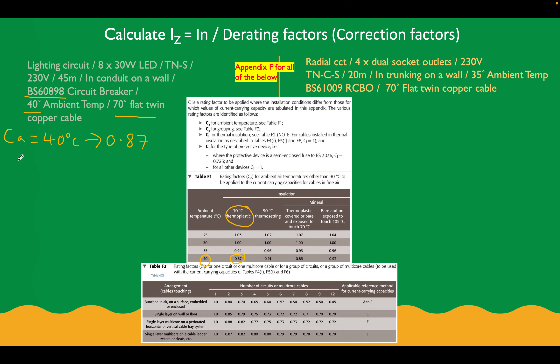We've also got a certain type of fuse, so CF — those are the only two correction factors we're going to include in our calculations. CF, for the type of protective device: where the protected device is a semi-enclosed fuse to BS3036, CF equals 0.725. For all other devices, CF is 1. We're not using a BS3036 fuse, so our CF is going to equal 1. We put it in there even though it seems redundant, so we can show our working.